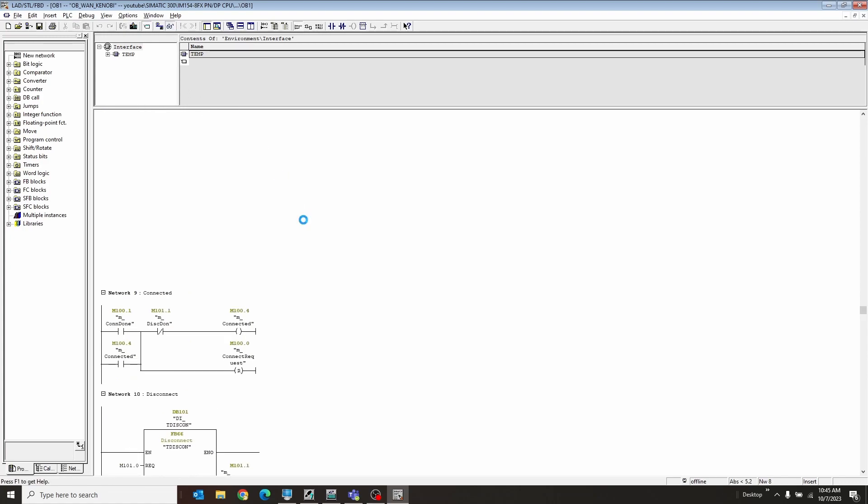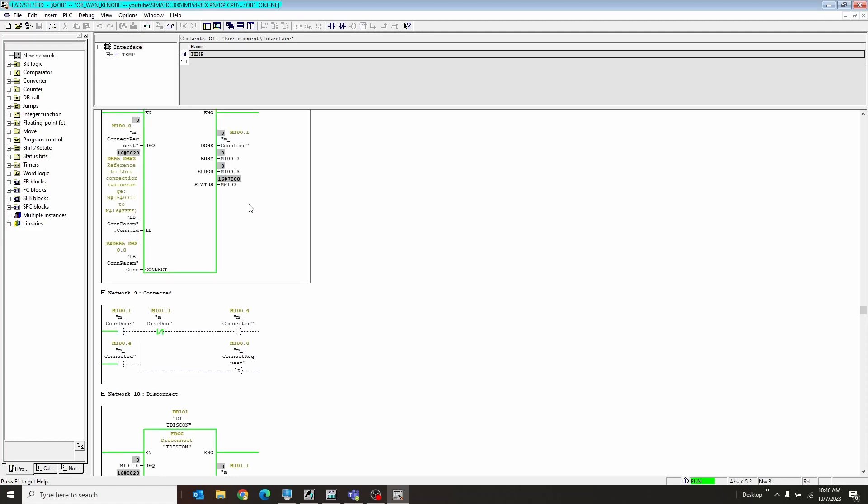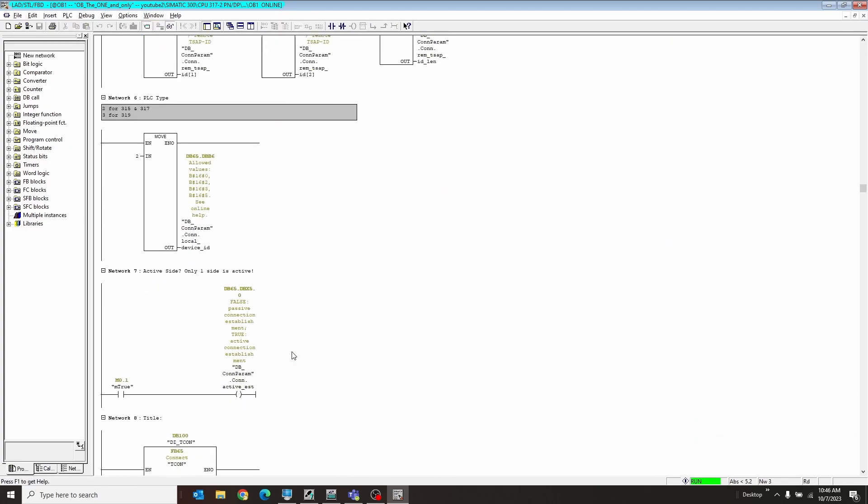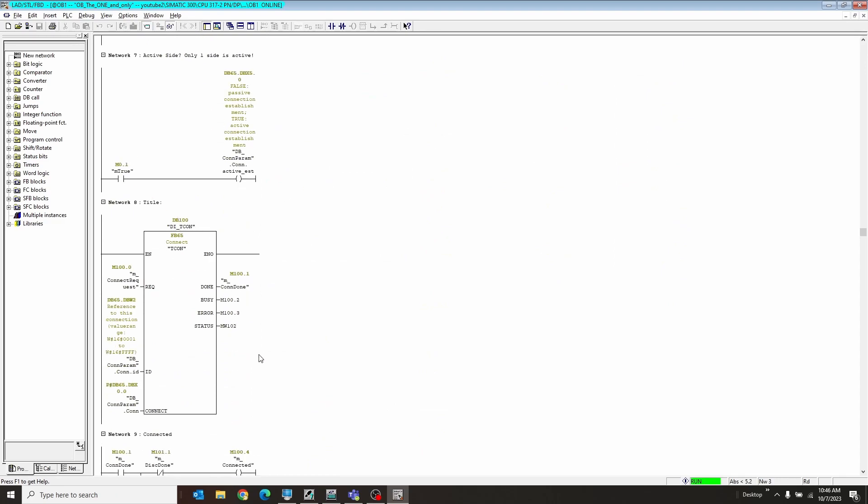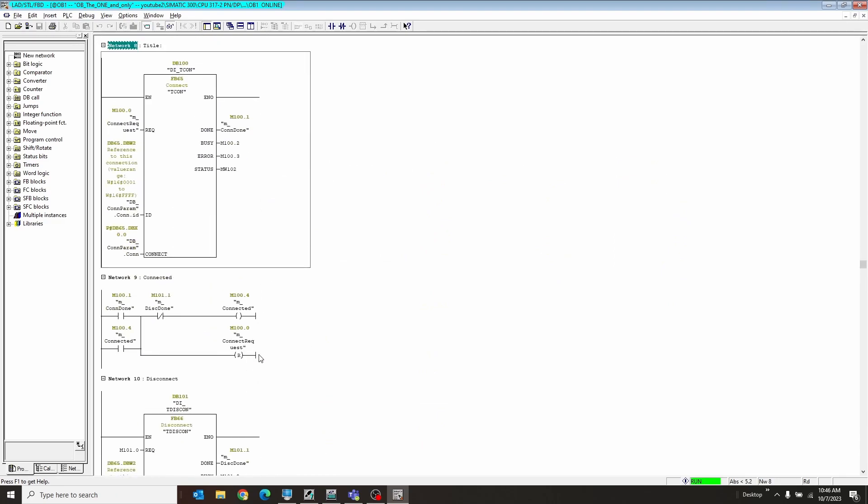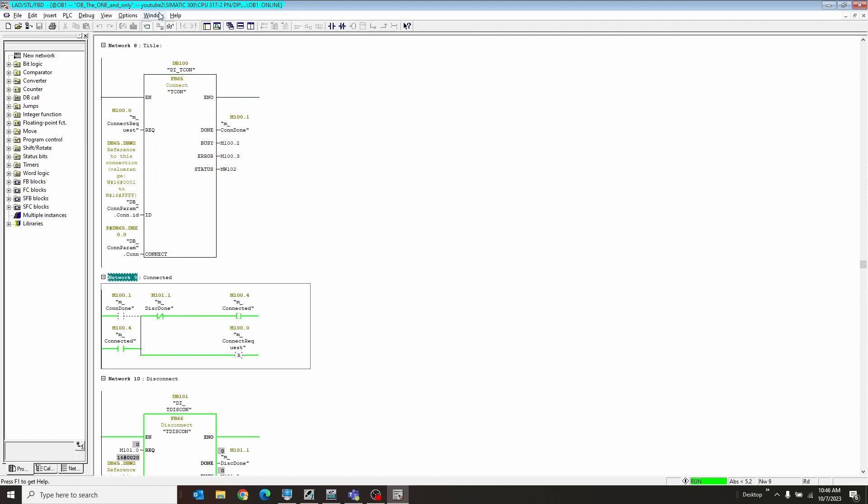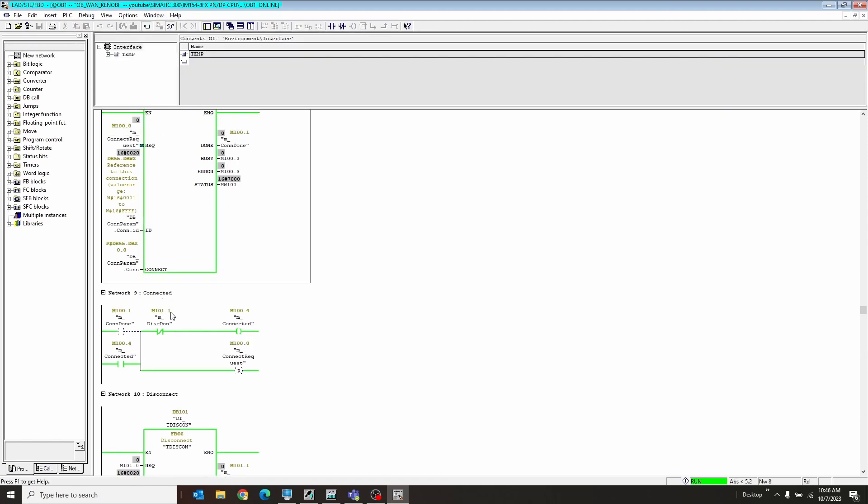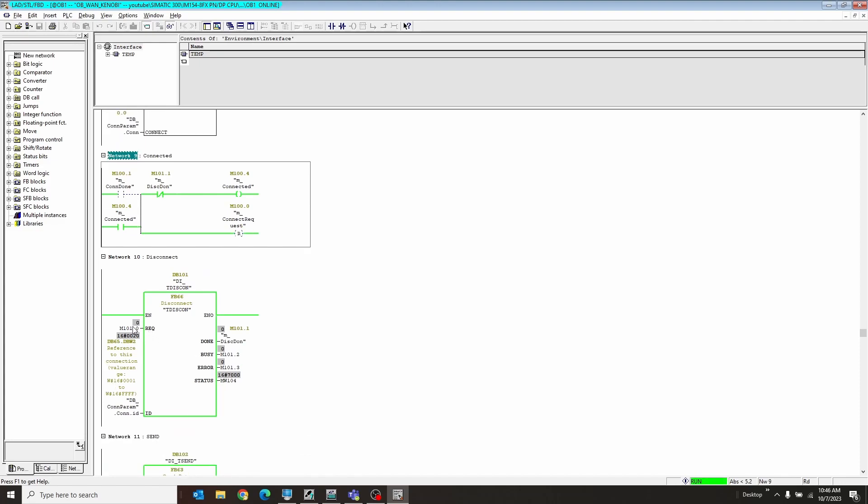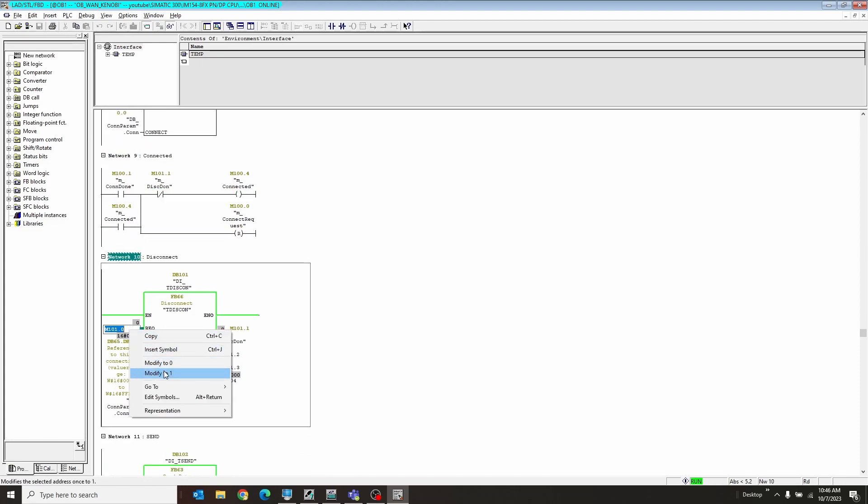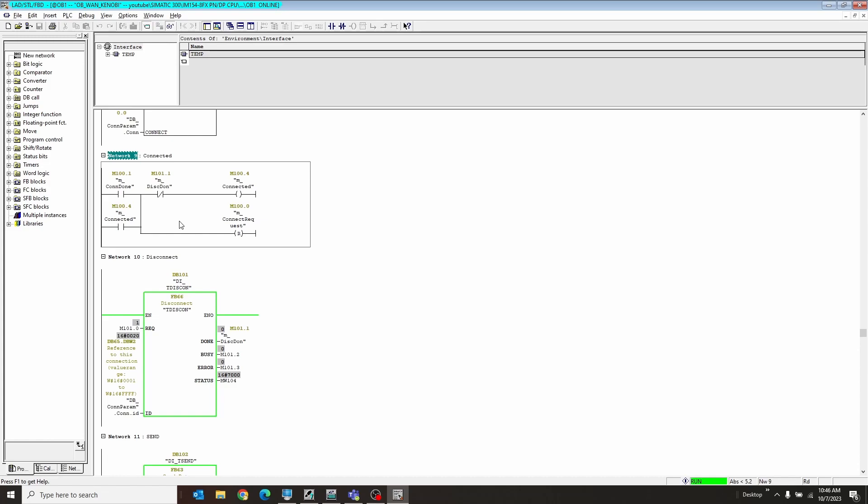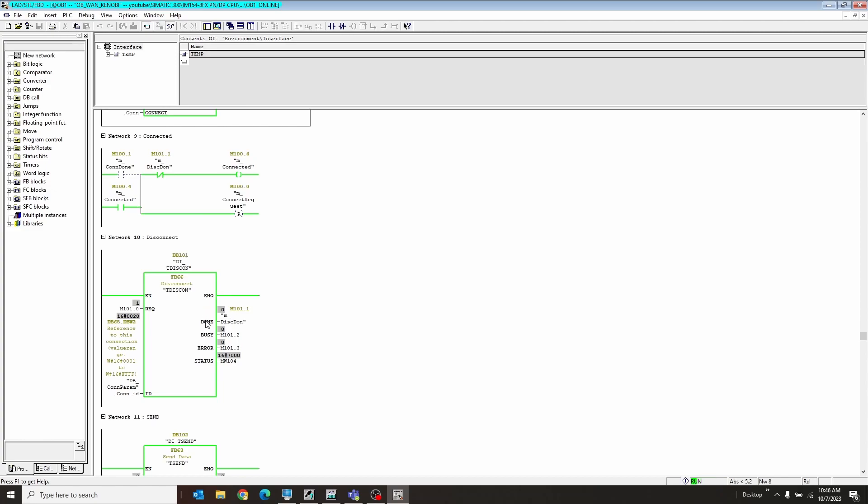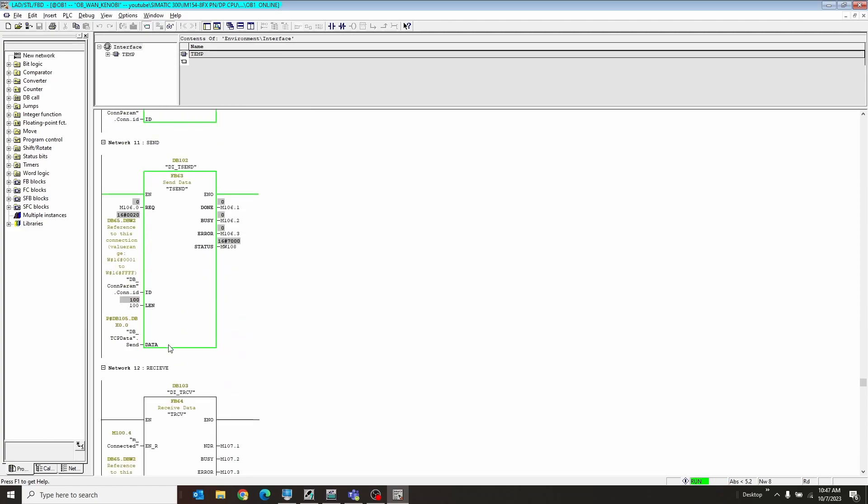I'm going to view him as well. Now, since he is not the active connection, we're going to want to turn on his request to connect. Hit OK. He's going to be busy. He's going to be requesting and busy until he gets connected from the active connection. We're going to go back to our first guy, the one who has the active connection. Go down to our T-CON here. And we're going to request that connection. And it happens in like one scan. See how this didn't come on and nothing happened over here because it did happen. And it sealed it in. That's why we didn't see it. So if we go back to our second PLC, we can see he got the connection and he is connected. Very cool. So if we want to disconnect this, we can disconnect this from either side. We can just say disconnect and that closed the connection here. And I can come back up to this side and reopen the connection. And there he is. He's connected. Easy peasy. So that's the disconnect.